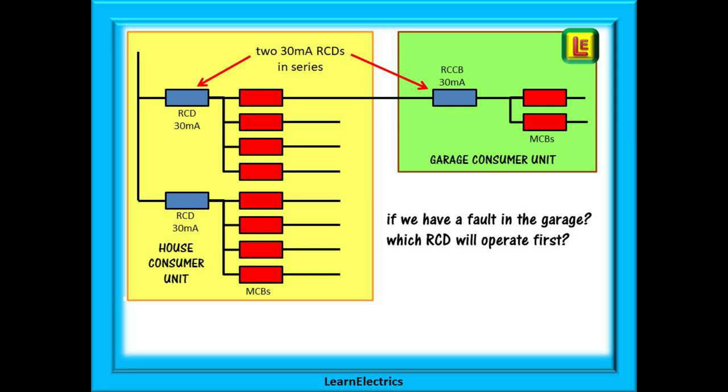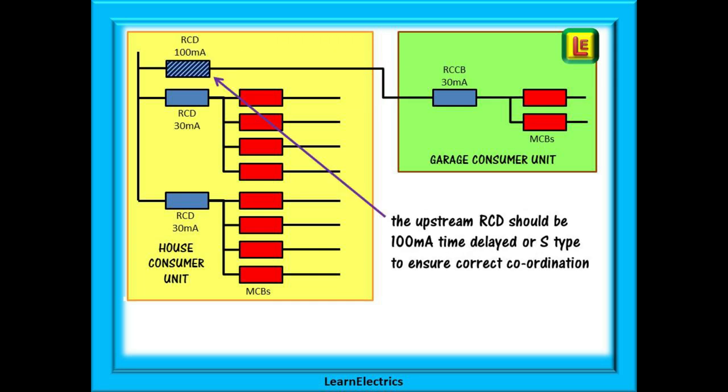We need to be certain that the garage RCCB only will trip. Correct coordination tells us that we should install a separate S type 100 milliamp RCD in the house consumer unit. This way we have achieved our three to one difference between devices. The 100 milliamp device will respond a little slower and the 30 milliamp device will operate first well before the larger device even thinks about it. Only the garage circuits will be affected.